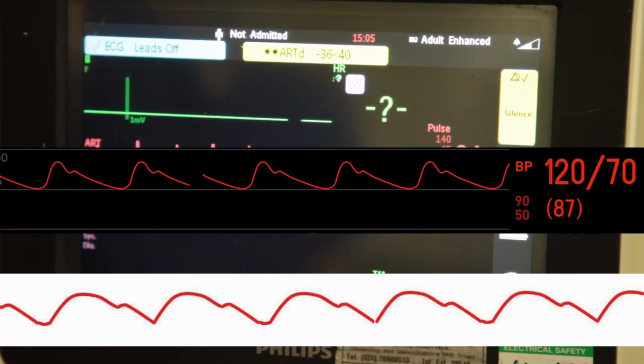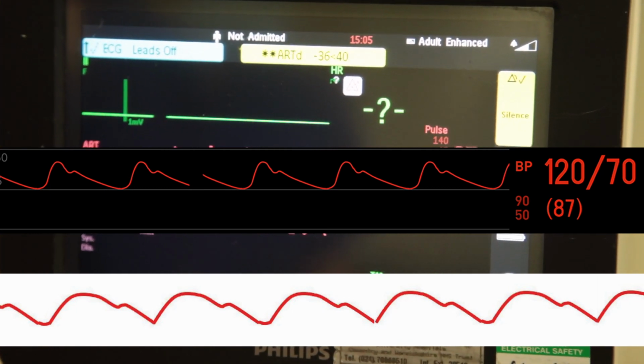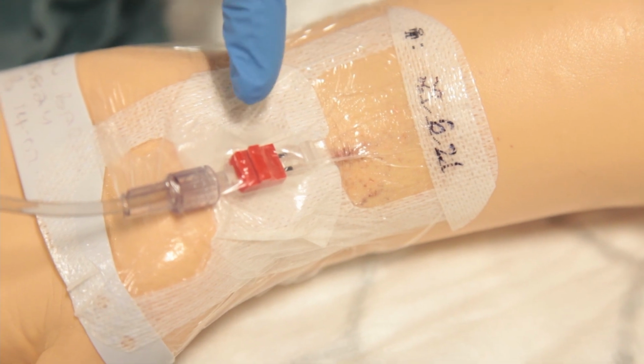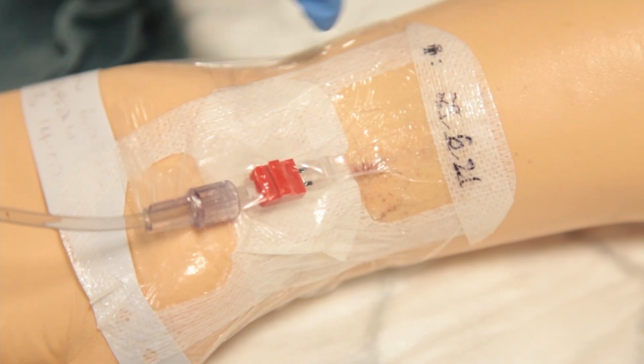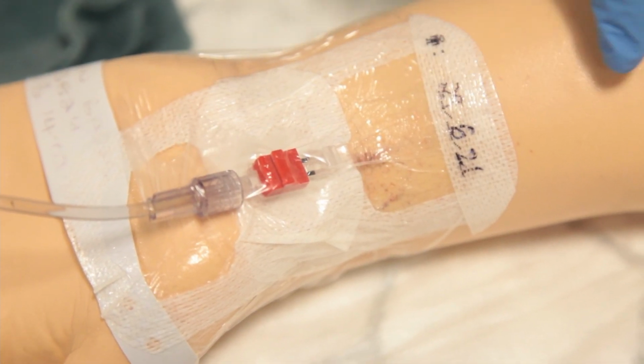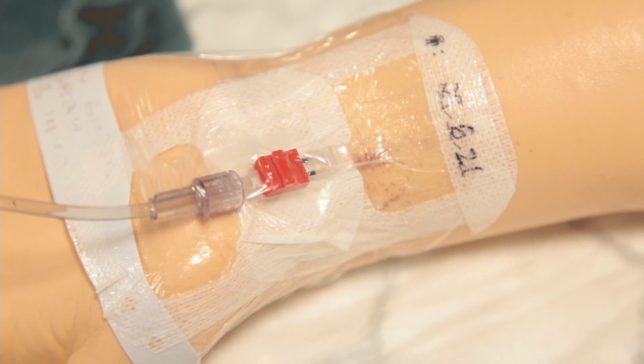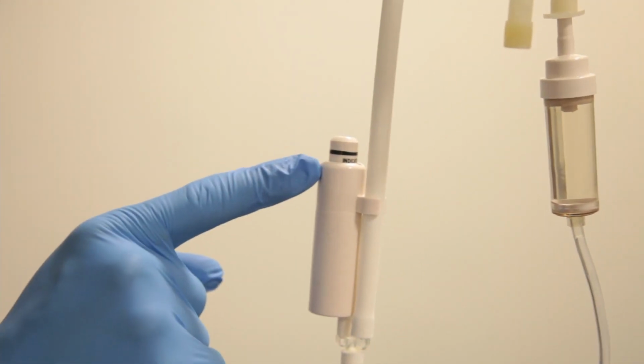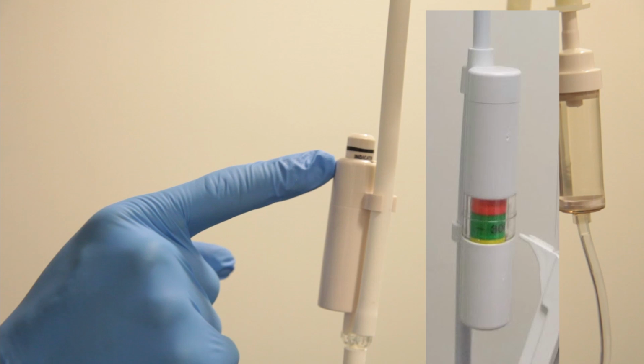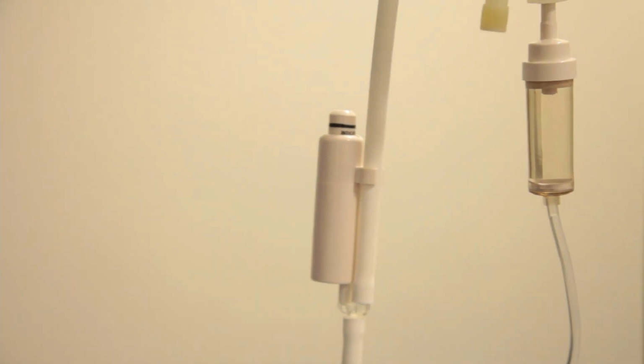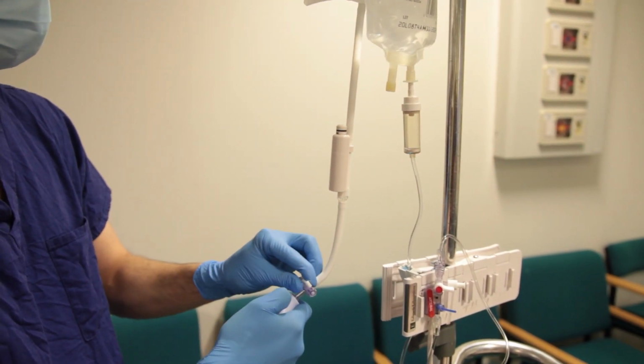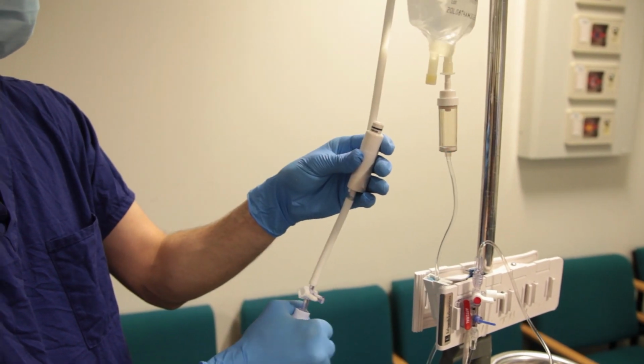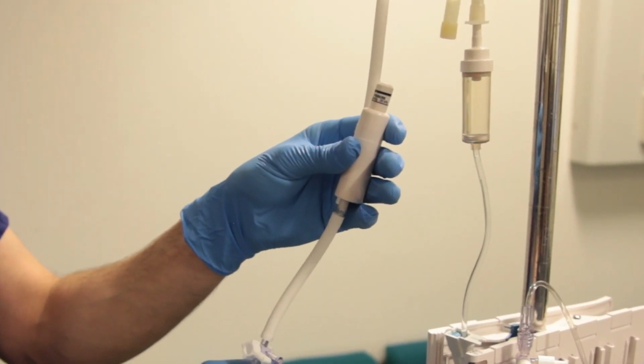A damped arterial trace. As mentioned before, air in the line may lead to the trace appearing more flat. Once again, you should inspect the cannula for any evidence of infection or disconnection. The issue may be air in the line, which can be fixed as described previously. Check the pressure gauge on your pressure bag. This may need more air being pumped in if the gauge is not lying within the green zone.